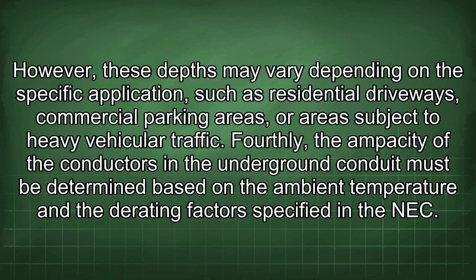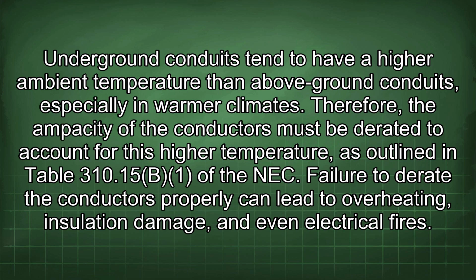to heavy vehicular traffic. Fourthly, the ampacity of the conductors in the underground conduit must be determined based on the ambient temperature and the derating factors specified in the NEC. Underground conduits tend to have a higher ambient temperature than above-ground conduits, especially in warmer climates. Therefore, the ampacity of the conductors must be derated to account for this higher temperature, as outlined in Table 310.15 of the NEC. Failure to derate the conductors properly can lead to overheating, insulation damage, and even electrical fires.